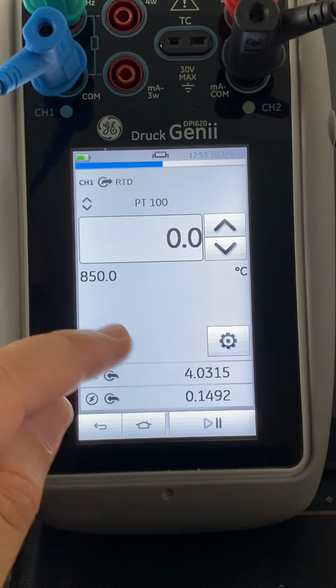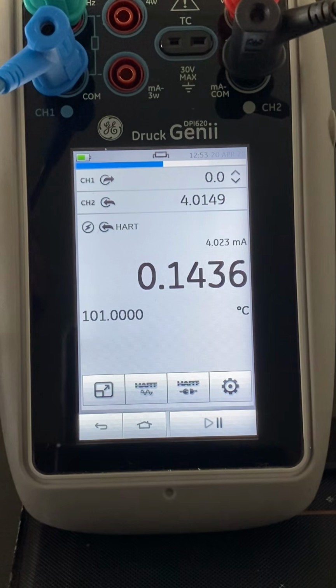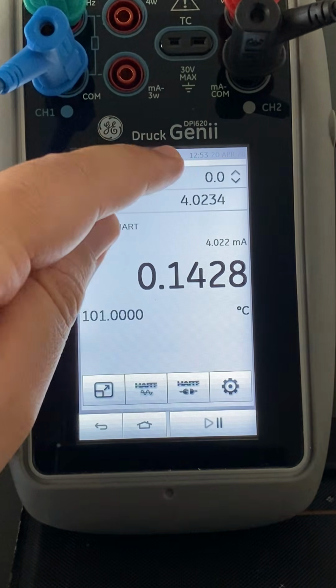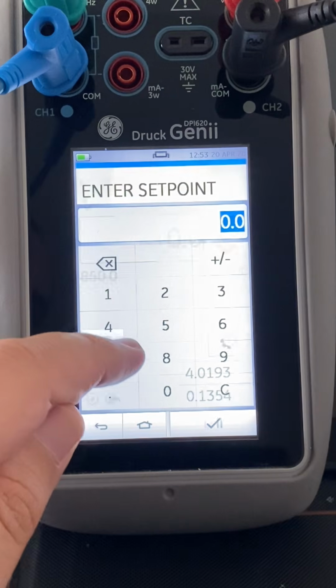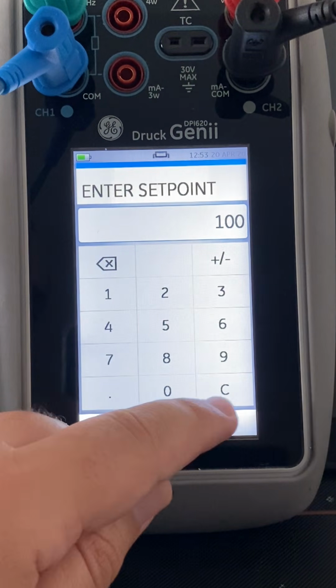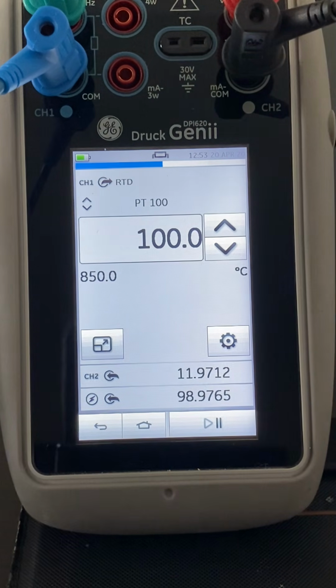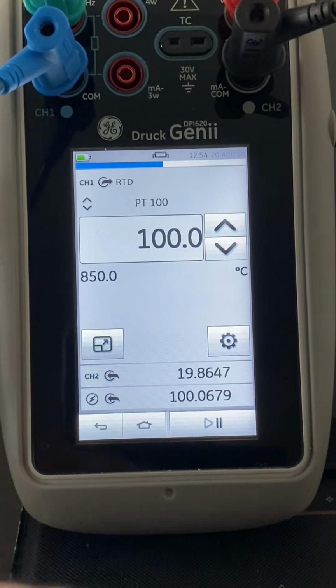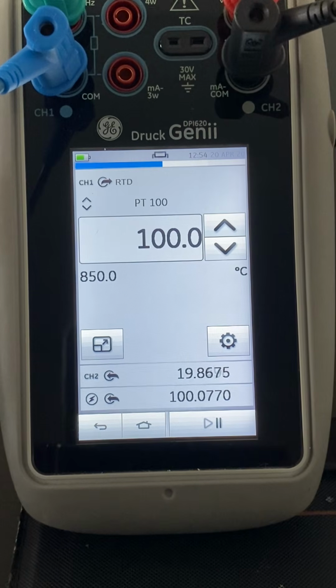So this is our transmitter. It's giving 4 milliamperes at 0 degrees Celsius. Just to give you an indication about the error, this is the 100 degrees on the input, and it gives us 19.84 milliamperes. So this is outside the tolerance, and we should go and make the adjustment. Okay, let's take it back to 0.